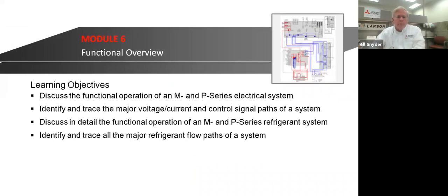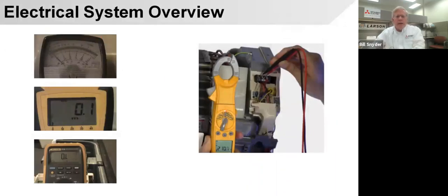Okay, I'm going to go right past these things and keep talking about the slides because we're kind of limited on our time today. When you're checking the voltages and the way the indoor unit or outdoor units work, we're checking between S1, S2, and S3. And there's also a ground here. S1 and S2 are line voltage, and we'll just drop our meter across there like they're showing in the diagram here. And in this case, we're reading 210 volts.